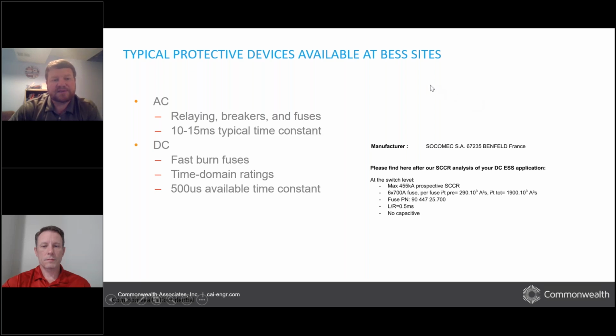Yeah. So just to put this in perspective, a lot of AC fuses and AC devices, even if the fuse is rated for DC operation, are going to have time constants in the 10 to 15 millisecond time range. Now we're talking cycle time range, which is what we're typically used to in AC systems. But the point we were trying to make is that for BESS, especially the lithium-ion technology BESS, which is predominant right now, specific fuses have to be selected that have time constants appropriate to these types of projects. We need those time constants to be in that 500 microsecond range. Just incredibly fast fuses that can help us with both short circuit problems and arc flash problems in the DC networks of batteries.